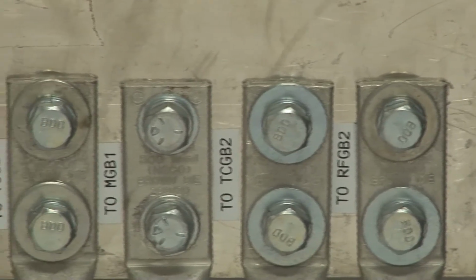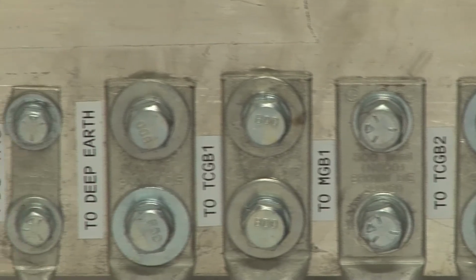We have had issues where we had electricians that did not properly torque equipment. What we've done to remedy that is we have a torquing scheme. The electricians have to document every connection that they have. They have to document the torque setting. They also have to use a paint pen to physically mark the screw or bolt inside the lug and show us that it was done properly.